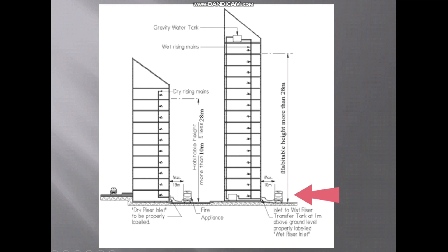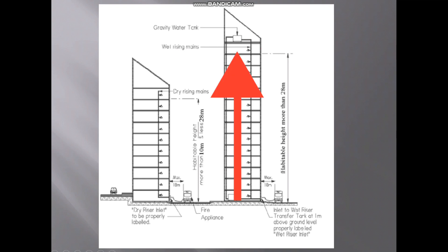In this example, this is the fire engine standing place — that may be the ground floor of this building. From here, for this building, you can see the gravity water tank is located in the roof. The habitable height is measured from ground level to the usable story floor level — that means up to this floor, not at the roof level.